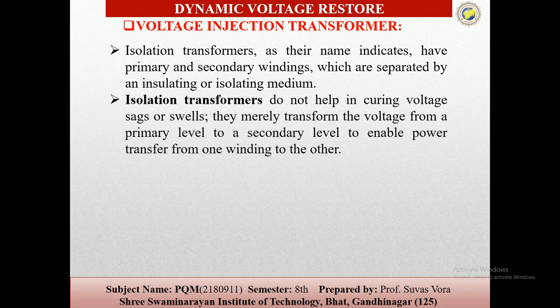In these systems the isolation transformer does not help in correcting the voltage sag or swell, but merely transforms the voltage from primary level to secondary level to enable the transfer of power from one winding to the other.